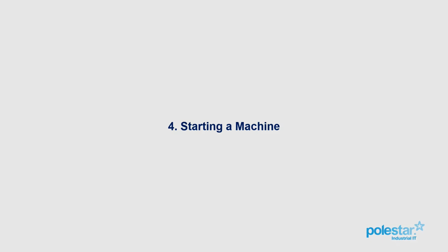So if you put 900 seconds and write that, the actions will take place at different times in the program. The number of actions is preset. The time at which each takes place and its duration is based upon the preset time you've set there. You cannot go any lower than 150. If you try going to 100 seconds, it writes back to 150. As you can see, the time the lamps are indicated is very low at that point, hence why we limit it to 150 seconds. Let's start a process on the machine.